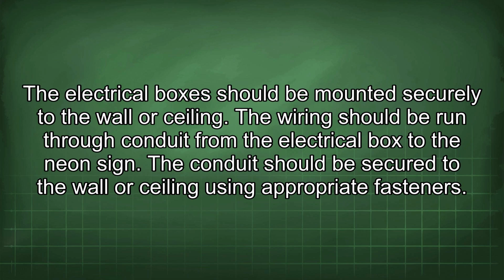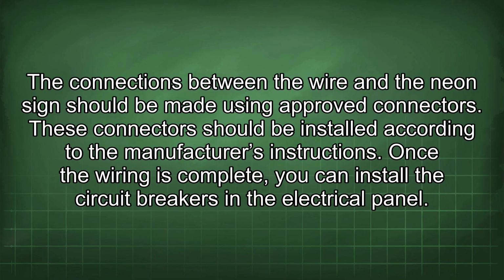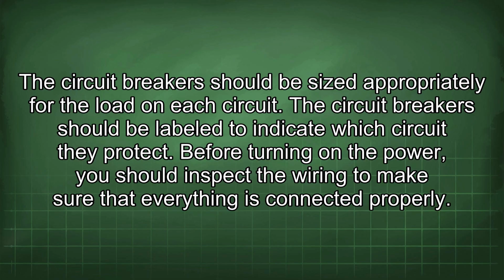The wiring should be run through conduit from the electrical box to the neon sign. The conduit should be secured to the wall or ceiling using appropriate fasteners. The connections between the wire and the neon sign should be made using approved connectors. These connectors should be installed according to the manufacturer's instructions. Once the wiring is complete, you can install the circuit breakers in the electrical panel. The circuit breakers should be sized appropriately for the load on each circuit. The circuit breakers should be labeled to indicate which circuit they protect.